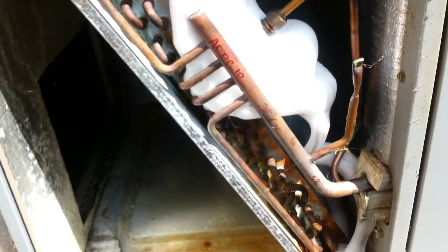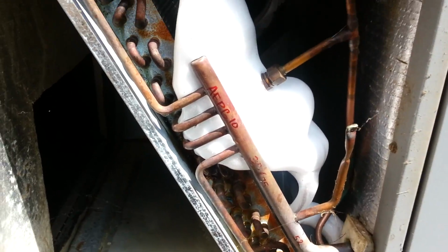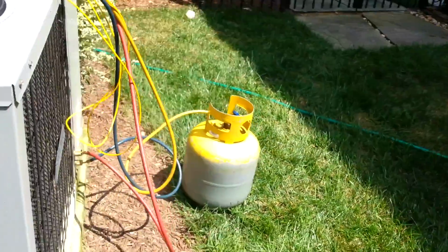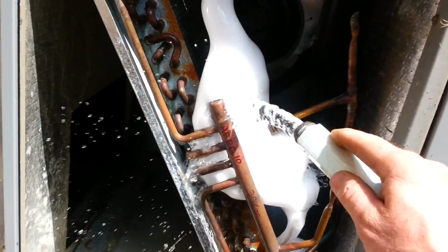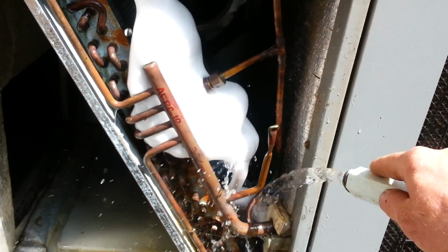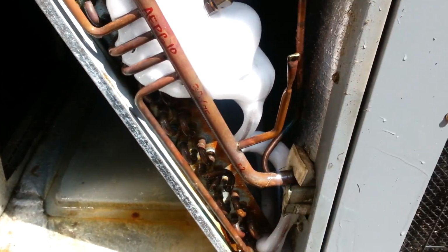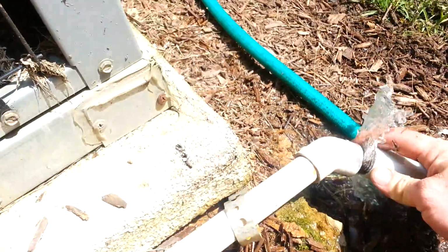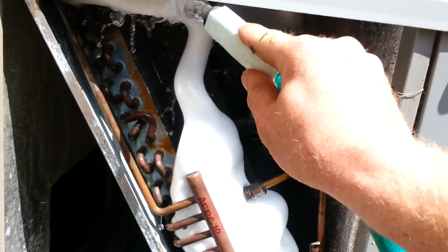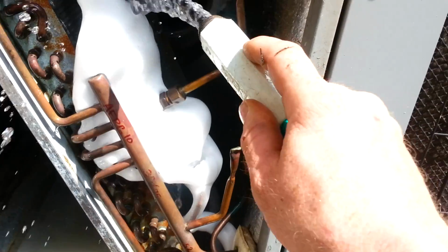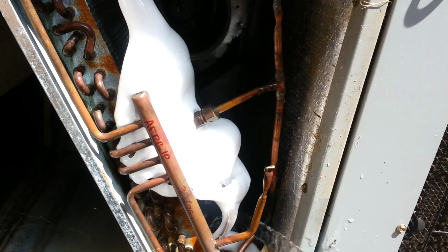This one also has a very dirty coil, which we'll be cleaning as well. But the very first thing we have to do is thaw the ice before we can do anything else. So we'll use the hose, which is the best way. Just simply put water on it. It'll melt very, very rapidly. Plus you want to check the drain, make sure that the drain is nice and clear. So once this is thawed, then we'll put it back together, and then we can begin charging.